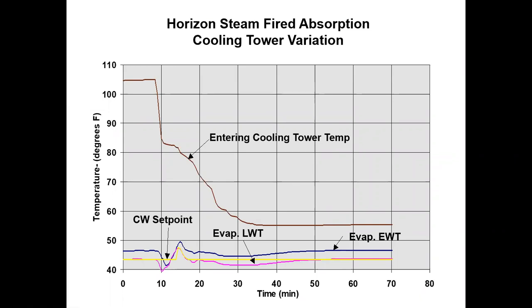Okay, so this is where the colder condenser water temperature was an issue as well, as far as crystallization. And so they dropped the cooling water temperature pretty radically, from 105 down here to about 55, over the course of, what is it, 10, 20, 30 minutes, something like that. And you see, initially the machine said, holy cow, what's going on here? So it took some pretty drastic action. But this is only a 20-minute transient, and it levels out pretty well. So this is just a demonstration that the controls have gotten much better. In the old days, this would have probably caused a shutdown.